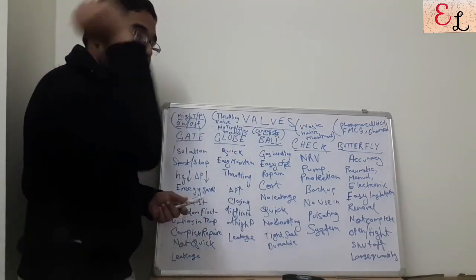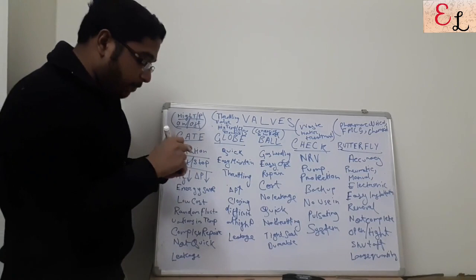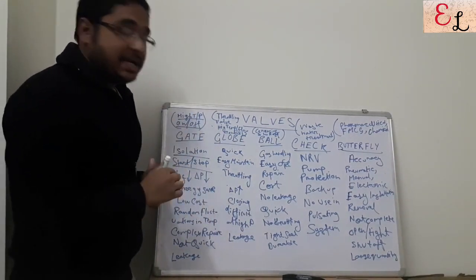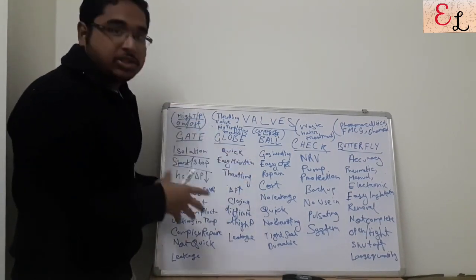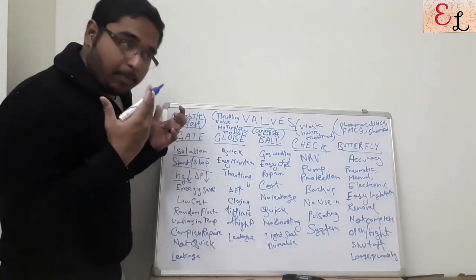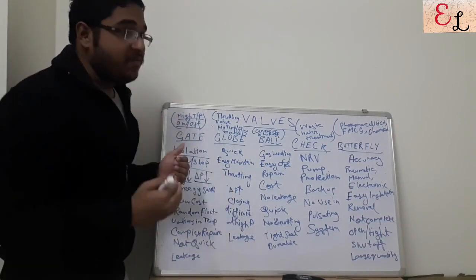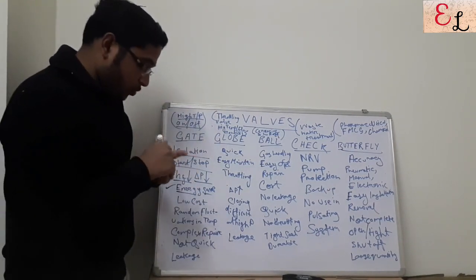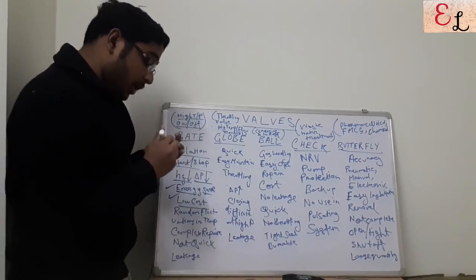Remember: when you need to close it completely or open it completely, you can use gate valves — it is for isolation, for starting or stopping the flow. Gate valve is preferred because when it is completely open, the frictional losses are very low. That is, Kc × V² / 2 — this is the form friction loss whenever a fluid passes through a valve. The Kc is very low for a gate valve, so the frictional loss and pressure drop are also low. There is therefore energy saving, and gate valves are very low cost.